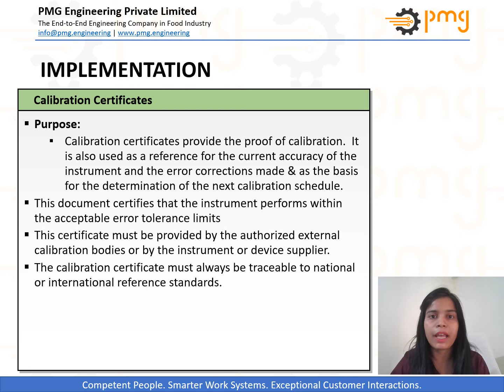Calibration of equipment, including calibration standards, must be traceable to international or other national metrology institutions and to a calibration service provider accredited under ISO standard 17025. The calibration certificate must contain specific information to assure compliance with standards.